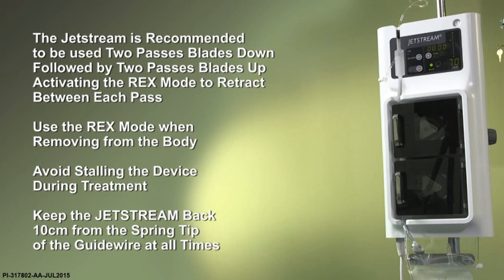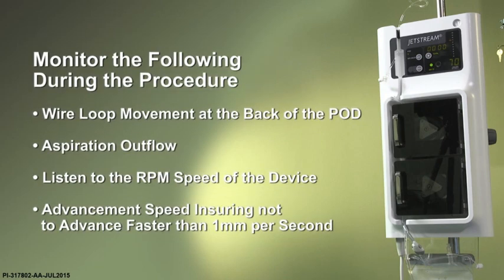We want to avoid stalling the device when treating. Keep the tip of the Jetstream 10 centimeters back from the tip of the guide wire at all times. We want to always monitor the wire loop movement in the back of the pod, our aspiration outflow, the RPM speed of the device, as well as the advancement speed when treating.